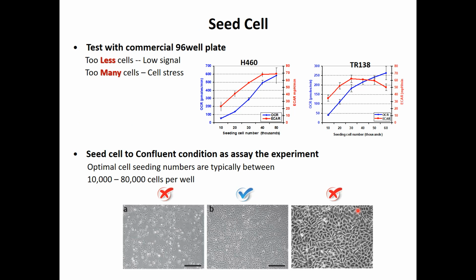And then the most important part is to prepare your cells. Cell number is a big issue. You have to make sure your cell number is not too low. If your cell number is too low, the signal may be too weak to detect. And if you have too many cells, then the cell metabolism balance will change. You can see here, in the beginning, the OCR and the ECAR are in a very stable ratio, but above 40,000 cells the balance changes. Here, for another cell line, at 30,000 the cell metabolism balance changes.